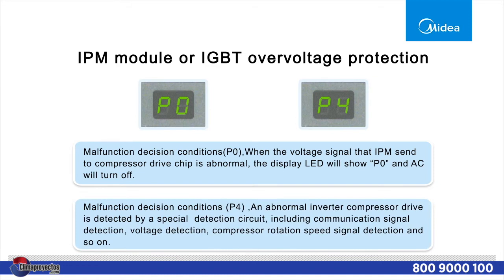Malfunction Decision Conditions, P0: When the voltage signal that IPM sends to the compressor drive chip is abnormal, the display LED will show P0 and the air conditioner will turn off.